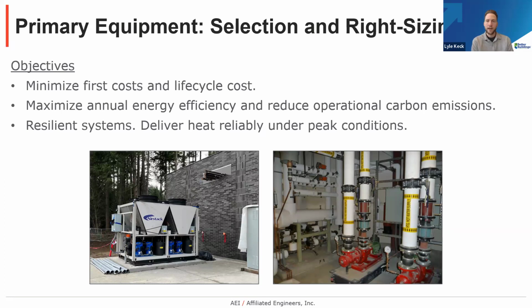At lower outdoor air ambient conditions, air source heat pumps derate significantly. They have defrost cycles. There's a lot of cycling. So having multiple sources of heat, or some type of higher temperature solution for peak conditions or critical operations, is another main objective of this type of boiler replacement project. And you can see the photo in the bottom left-hand corner here is an air source heat pump being installed in a zero energy capable laboratory facility here in Washington. Next slide.